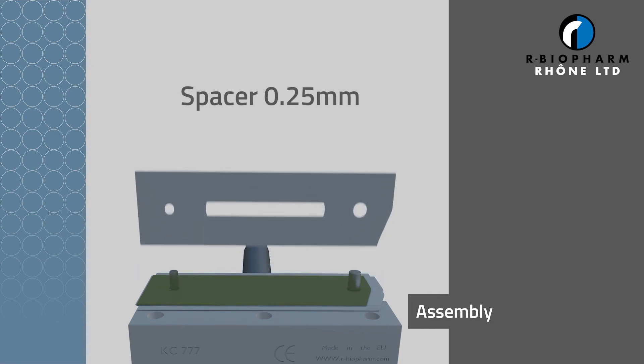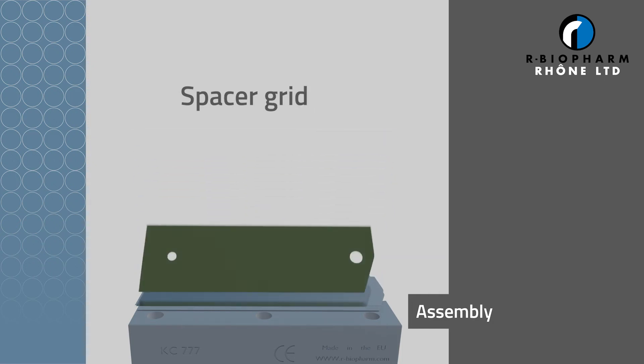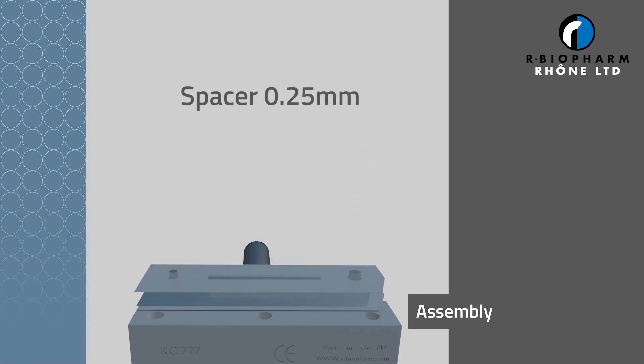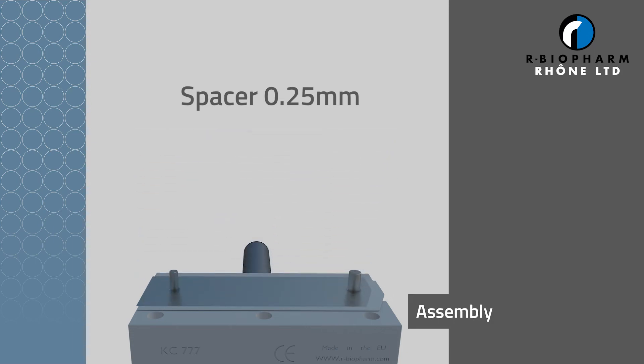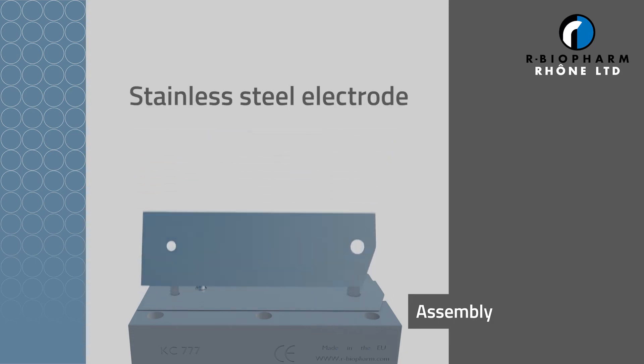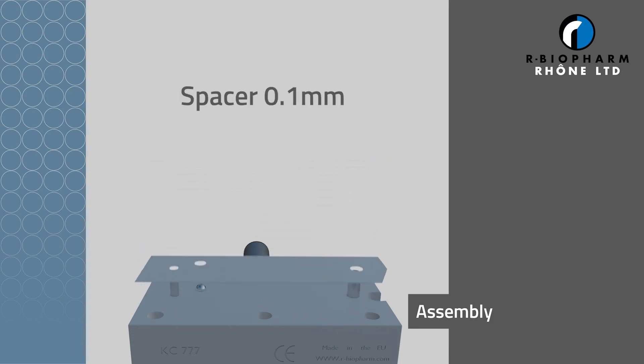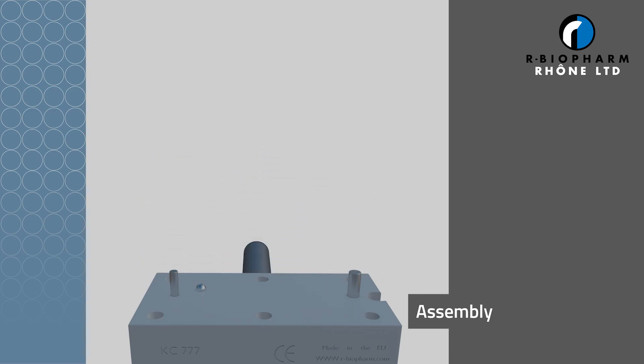The electric current generates the derivatization agent, bromine, online from potassium bromide and nitric acid, which are present in the mobile phase. This results in an increase in the fluorescence signal of the modified aflatoxins.